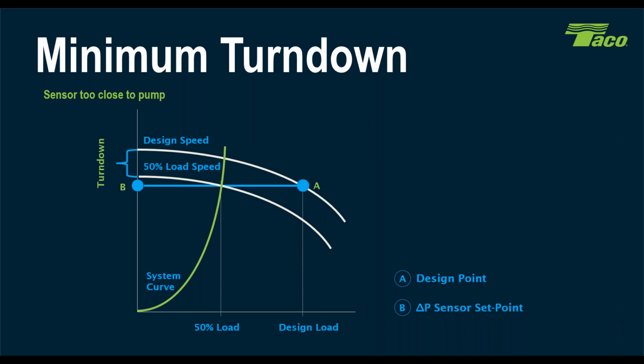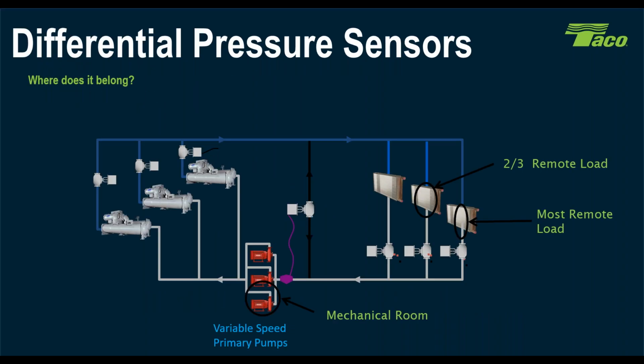Yes, so if you go back, if I can get my cursor to cooperate. If we go back to my drawing, if you put the DP sensor here across this pump set, so it'd be from here to here, that's where you don't want it. That is the absolute worst place in the world to put that DP transmitter.